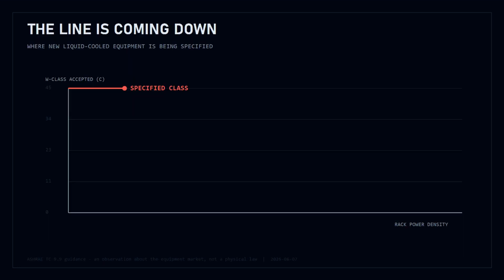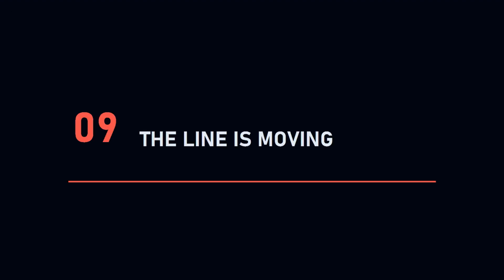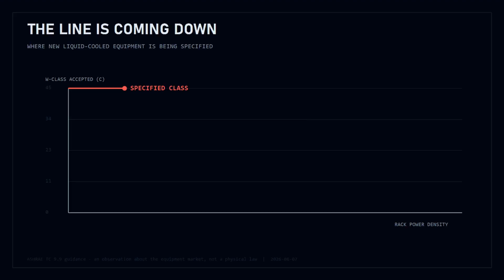One more thing, and it is the part an operator should worry about. The W classes are not evenly spaced and they are not fixed. ASHRAE's guidance notes that the capability to run at the warm end, W45, is not spreading the way it was expected to, and that a good deal of new liquid-cooled equipment is being specified back at W32 and W27 because chip junction limits have not moved as fast as chip power has. I am quoting that carefully because it is an observation about the equipment market, not a physical law.